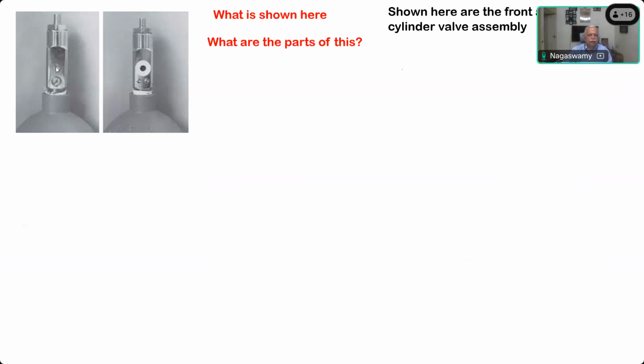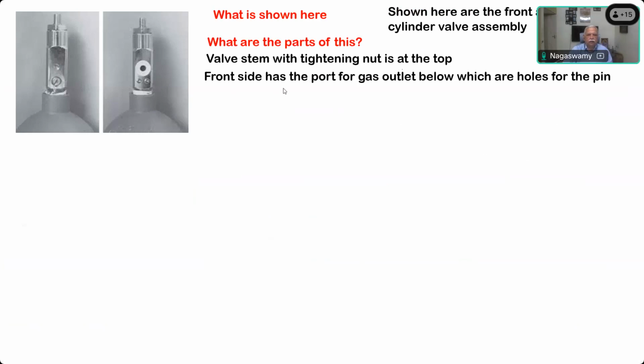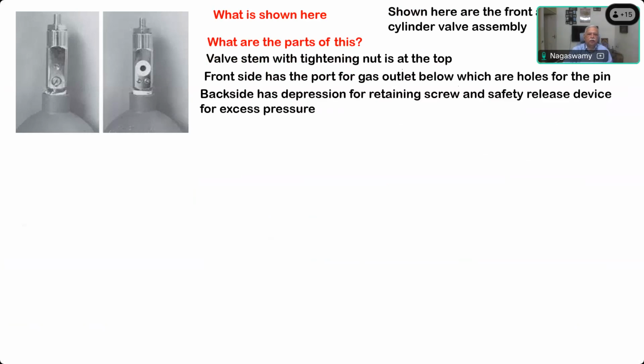This central conical depression is for the retaining screw to come in. And there is another screw-like thing which you will see here. What is that? Pressure relief valve. Very good. This is the valve stem with the tightening nut at the top. The front side has the port for gas outlet, below which are the holes for the pin index pins to be seated. The back side has a depression for the retaining screw and a safety relief valve for excess pressure.